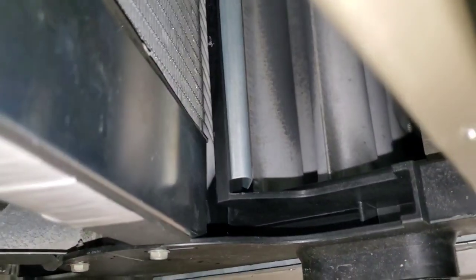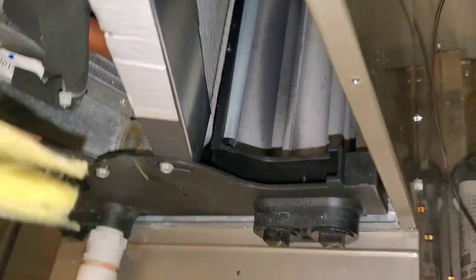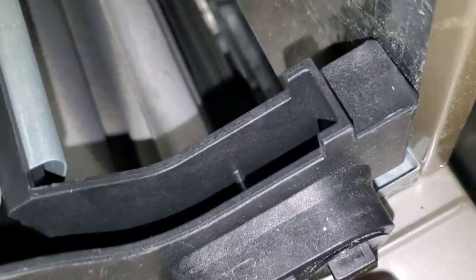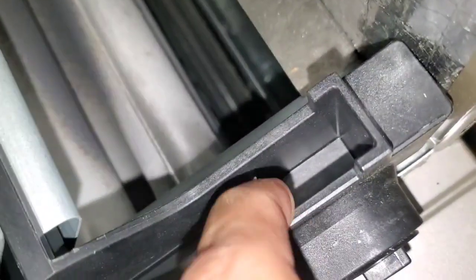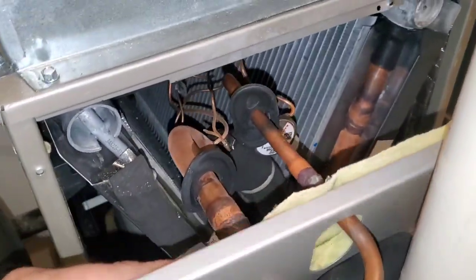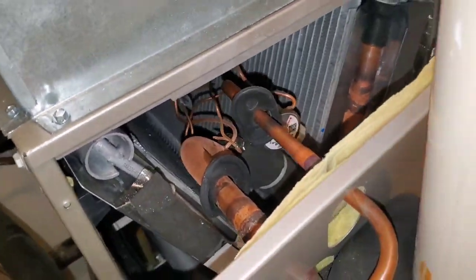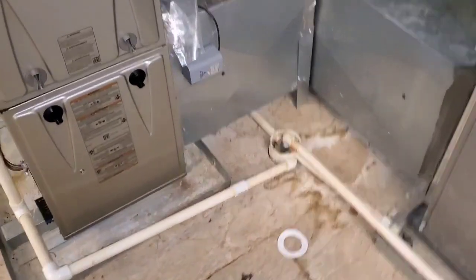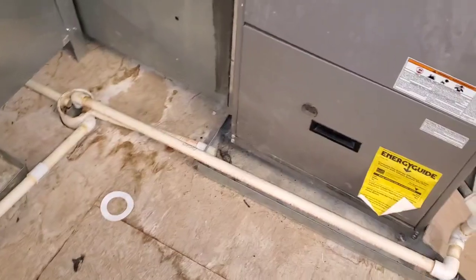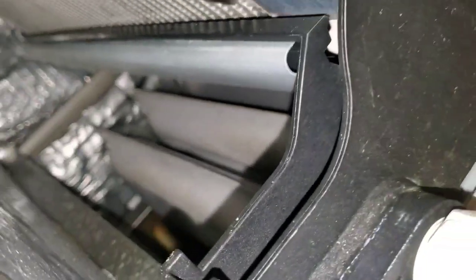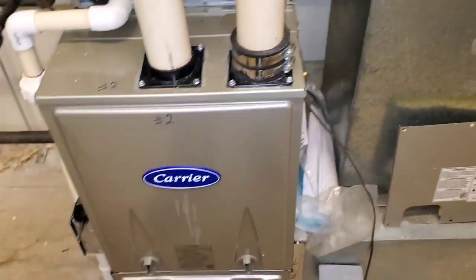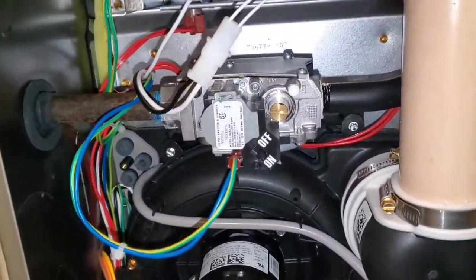I don't see a water line in there or nothing. In fact, there's no water over in this little compartment. Inside the evaporator compartment, we got no frost pattern. I just turned it off a few seconds ago. There's the heat exchanger. That looks fine. Let me open up the blower compartment and look for evidence that water has been dripping in there. That little thing there, so that's not wet.